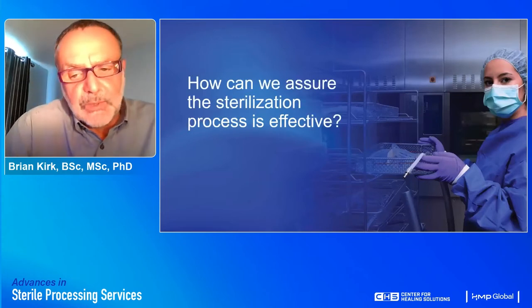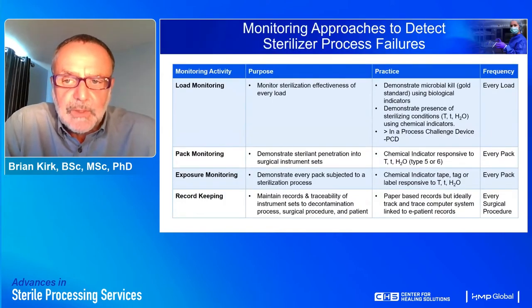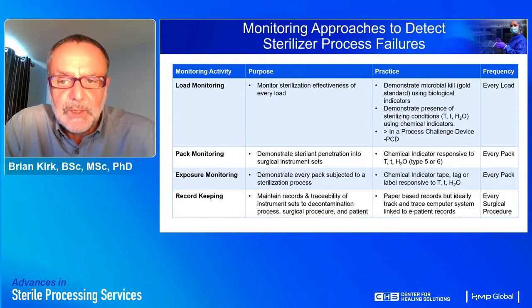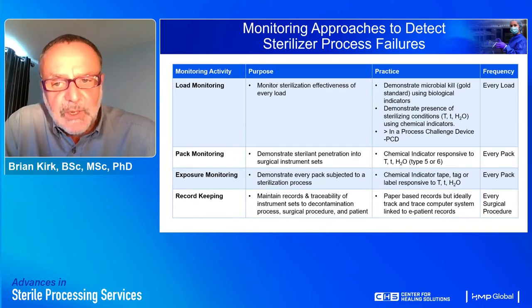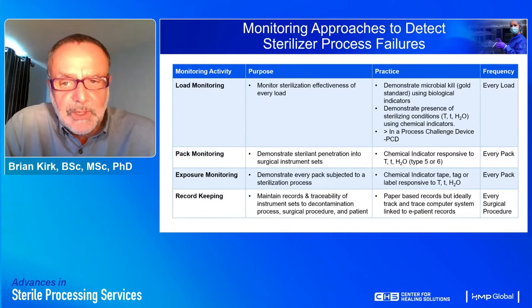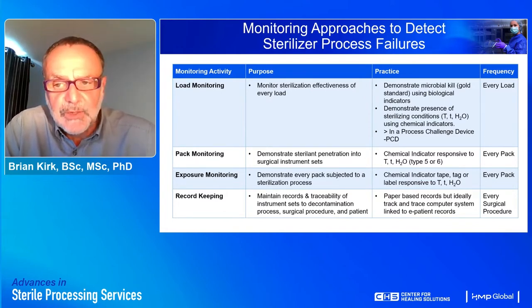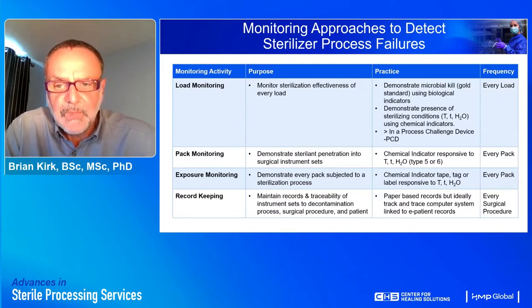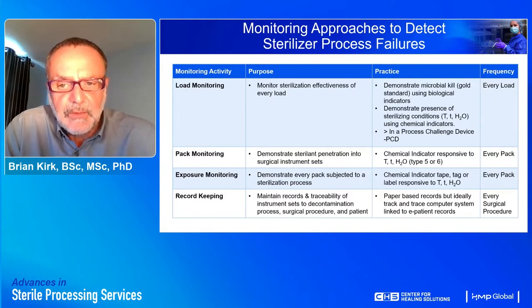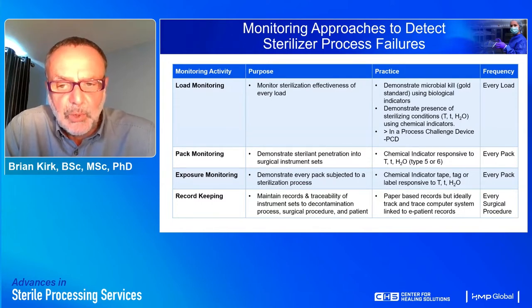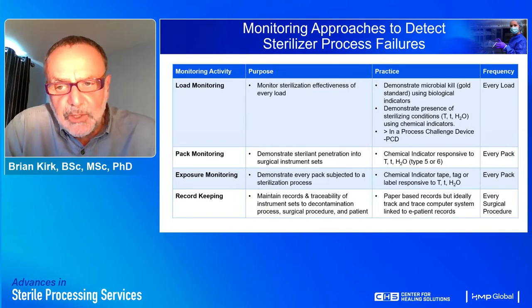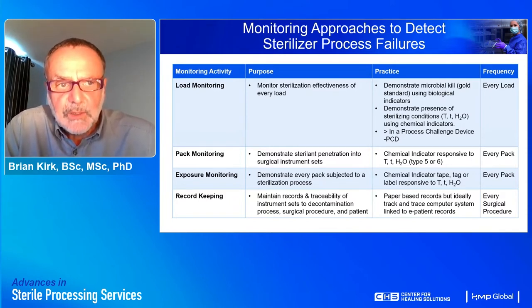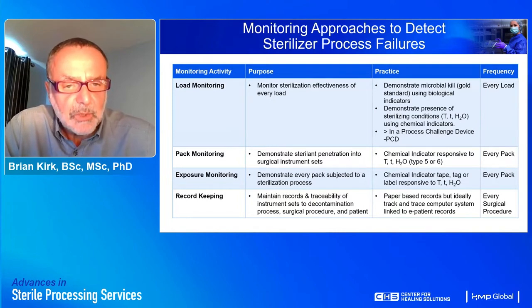To ensure the sterilization process is effective, a combination of actions should be used to detect possible process failures and provide evidence of an effective process. The first step is load monitoring, carried out using biological indicators — preferably enclosed within a process challenge device — along with examination of the process data produced by the sterilizer. Pack monitoring involves placing a chemical indicator in every pack, providing evidence that sterilant has actually penetrated through the packaging material to the point of placement. These indicators are particularly useful for operating room teams as evidence that a pack is suitable for use, and this is actually one of the requirements of the WHO surgical safety checklist.